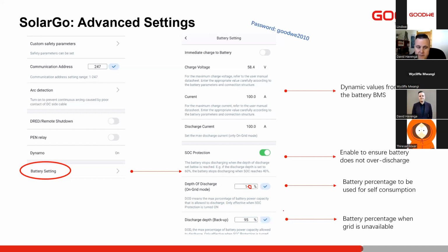And yeah, for the off-grid, typically we leave this at the default value for off-grid scenarios. So this battery can go to 95%, that's on here. So we'll use 95% of the battery when the grid fails.